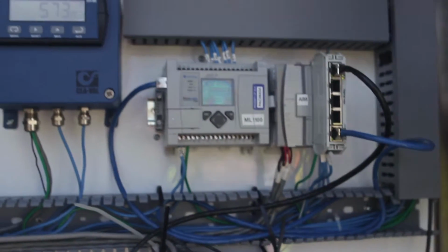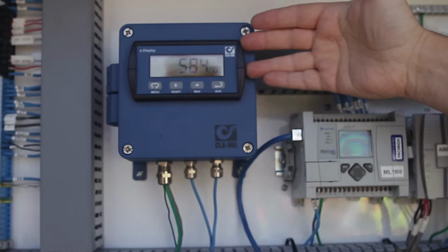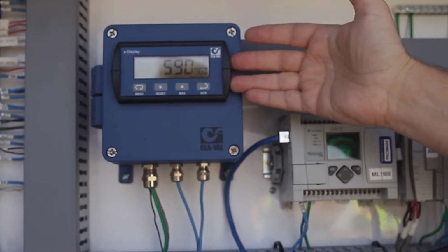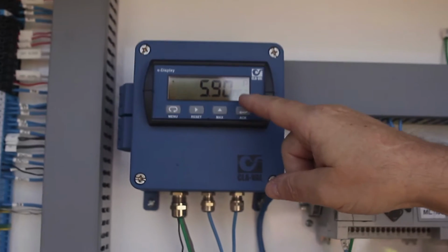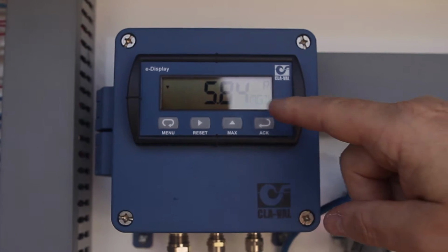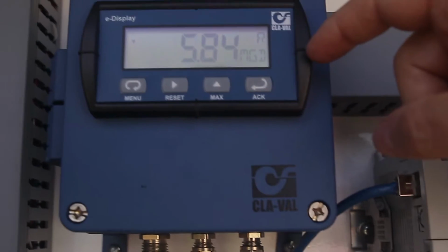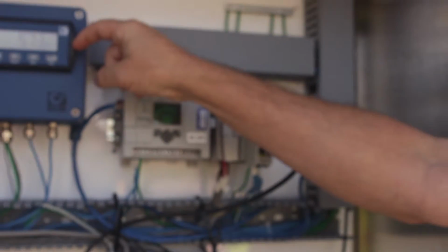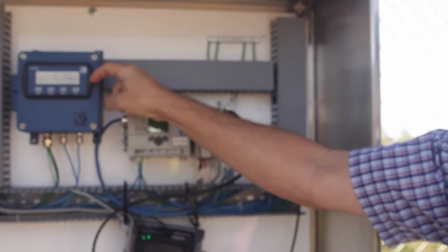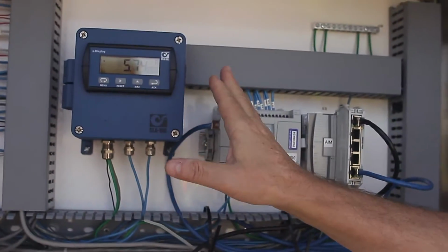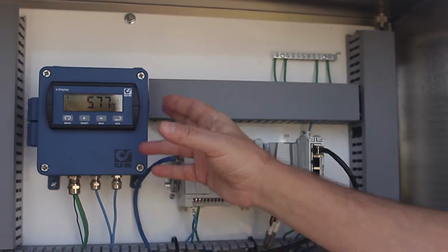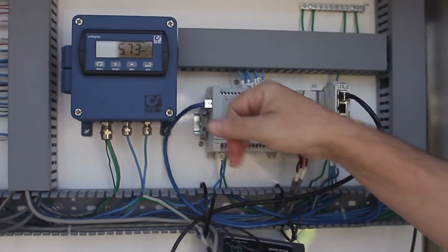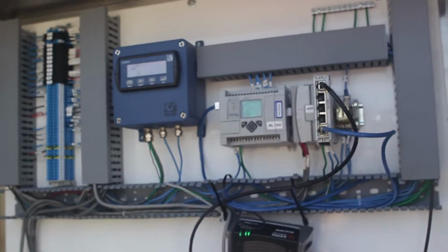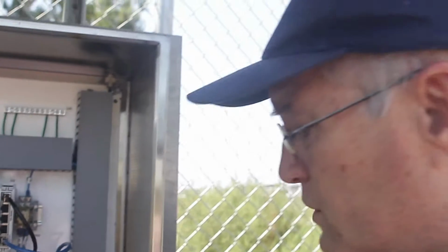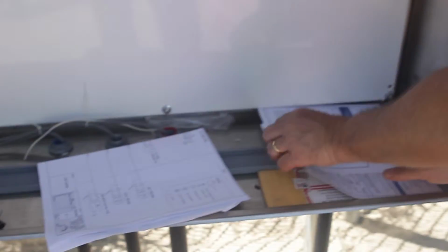We have originally programmed the meter itself. It comes from the factory in gallons per minute scaling. Since the customer wanted MGD, we rescaled to show MGD, not GAL, and we rescaled on a 16-inch valve. The full scale is 14,000 gallons per minute, which equals just a little over 20 MGD. So we rescaled in the programming, so it's already finished scaling. We scaled the total to read in millions of gallons, and they're just counting it here. So it's very simple setup, and all of the documentation is available on our website, and we will send the customer a full programming manual.